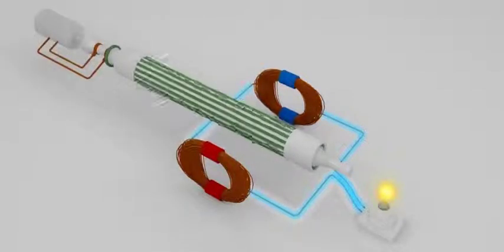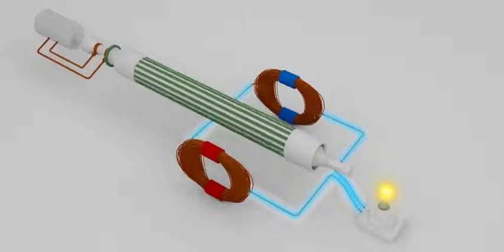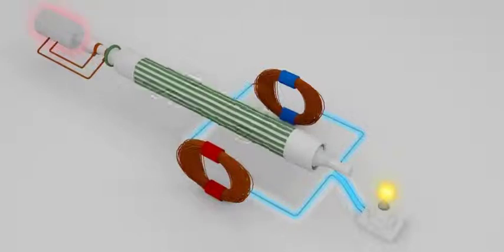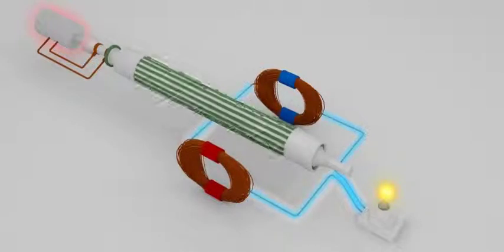This is overcome by using a heavy rotor with copper windings and creating a spinning electromagnet. A smaller generator attached to the same shaft provides the power for the field. This is called the exciter. The armature windings on a large generator are built with many conductors and output 3 conductors or phases that are necessary for running large machines and for transmitting to the grid.